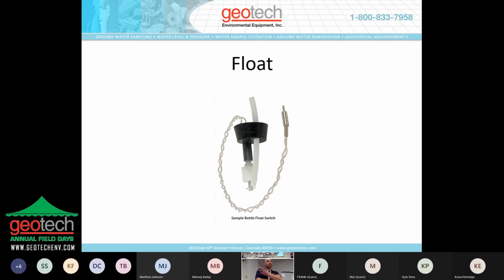So you're asking if it purges after every sample collection? Yes, it does. And then it doesn't re-purge before you collect the next sample, right? No, it back flushes after it collects a sample, and then it will just turn on the next hour. I think the line is pitched so it doesn't allow any retention in the tubing.